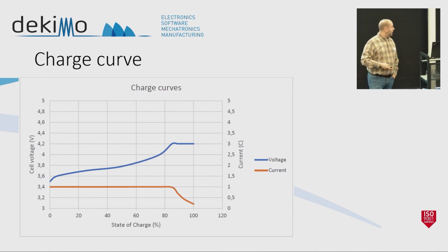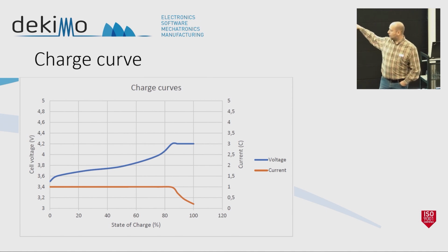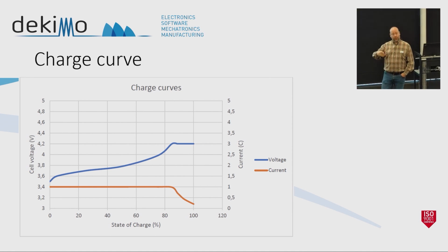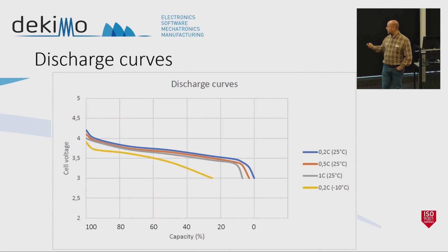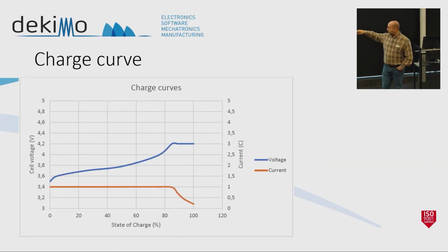In the charge curve, you have two regions that you can see. The first region is on the left side, from 0 to 80%, where you charge the battery using a constant current power supply. So you push, for example, 1 amp, 2 amp, 10 amps into the battery, and the battery voltage will rise until the capacity is up to somewhere between 70 and 80%, depending on the chemistry you're using.